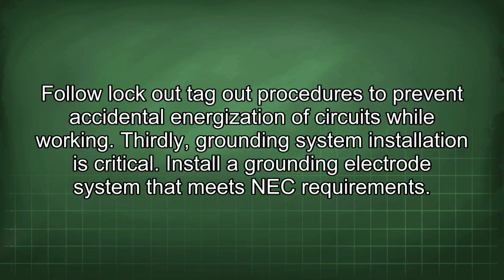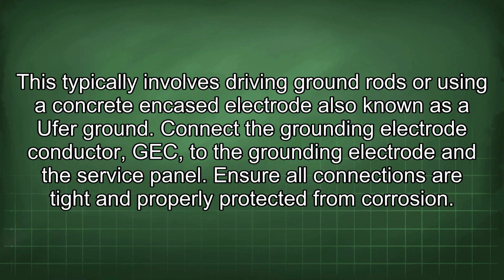Thirdly, grounding system installation is critical. Install a grounding electrode system that meets NEC requirements. This typically involves driving ground rods or using a concrete-encased electrode, also known as a UFER ground. Connect the grounding electrode conductor (GEC) to the grounding electrode and the service panel. Ensure all connections are tight and properly protected from corrosion.